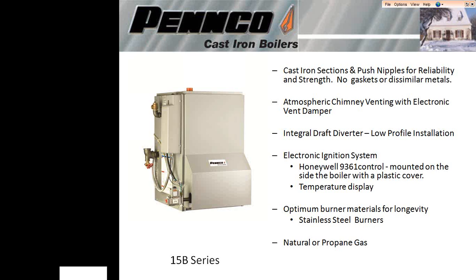If you look at the picture, you'll see there's a box on the left side, and in that box there's a Honeywell control, which is the boiler operating control. So by stepping down from hydro level to Honeywell, there's another cost savings as well. The nice thing about the 15B is that all the piping and controls are on the left side of the boiler. So if you have customers that need to pipe their supply and return on the left side, where on the DXL it's on the right side, you have that option with the Pennco product.